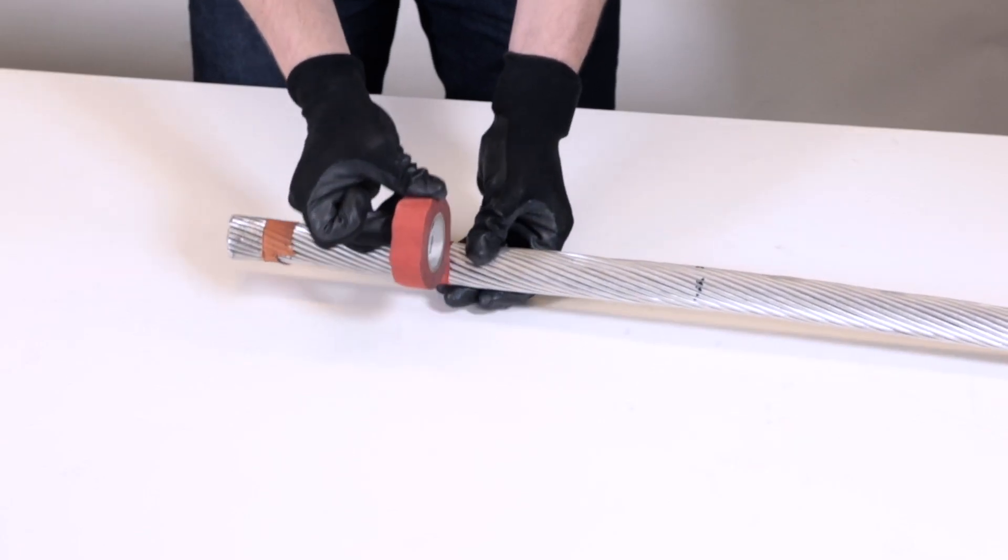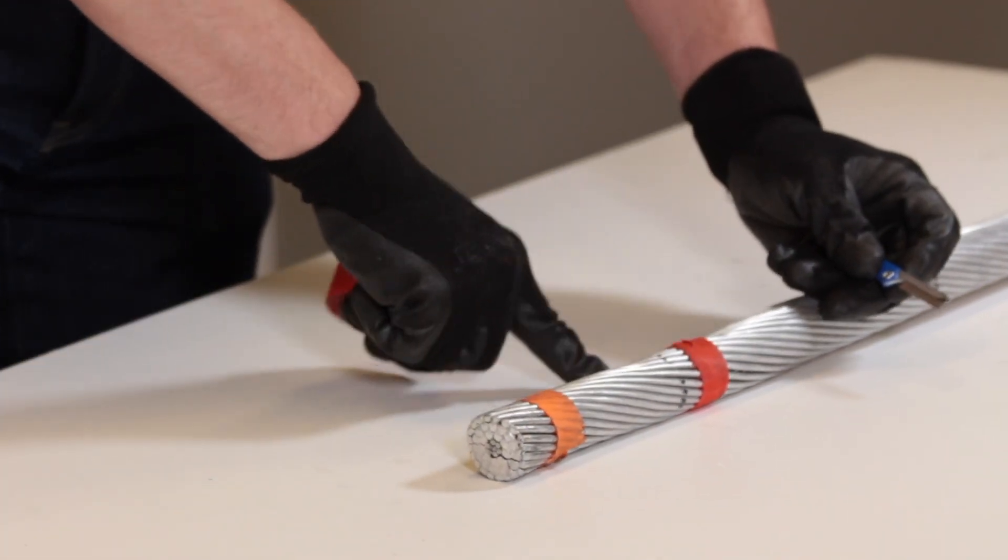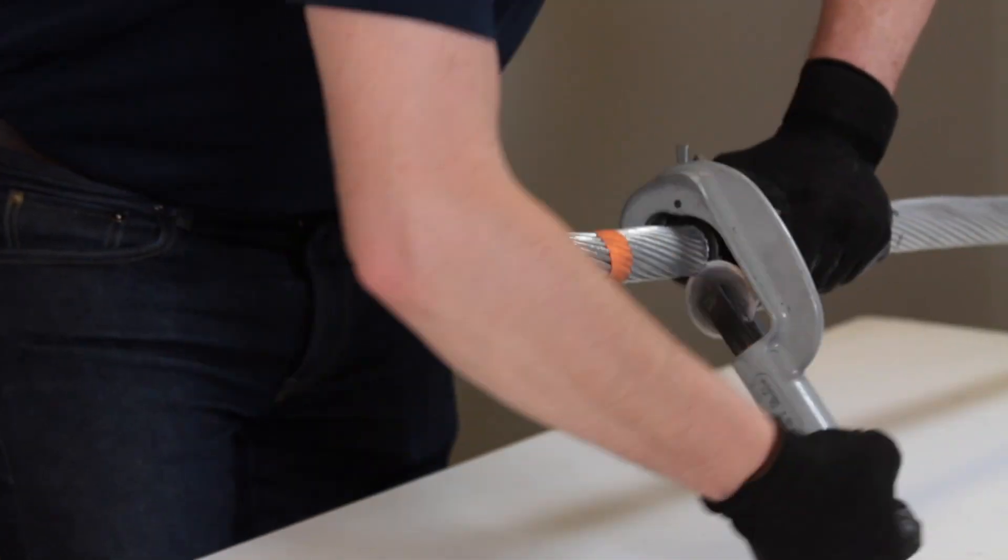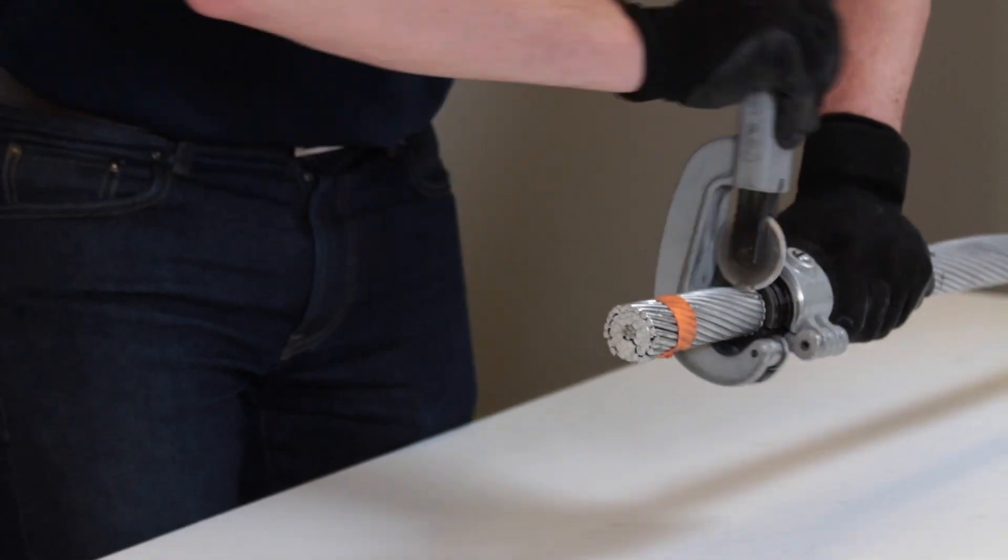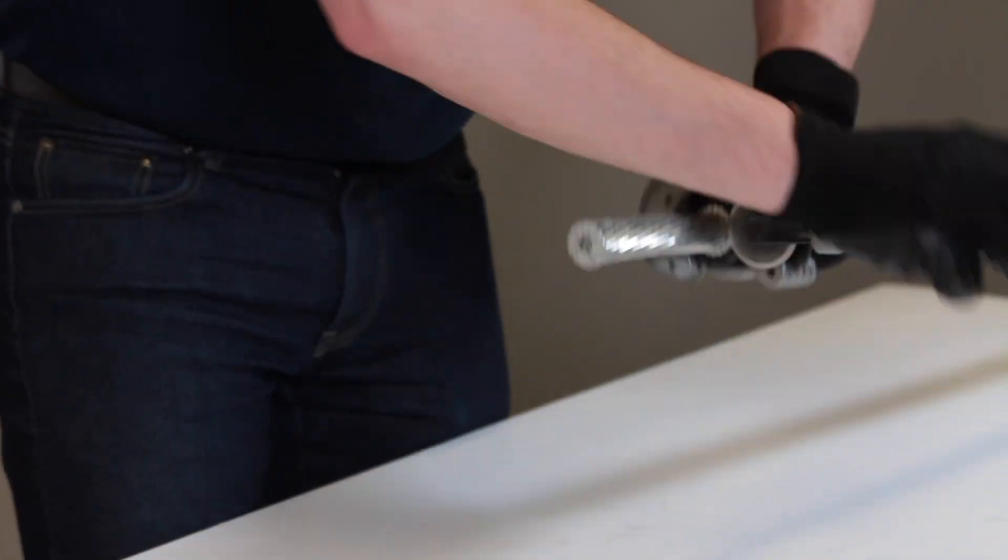Apply tape approximately one inch back from the cutting mark to secure the aluminum strands and maintain the conductor diameter after the cut is made. Cut the outer aluminum strands at the cutting mark to expose the steel core. Take care not to damage the steel core strands during this process.